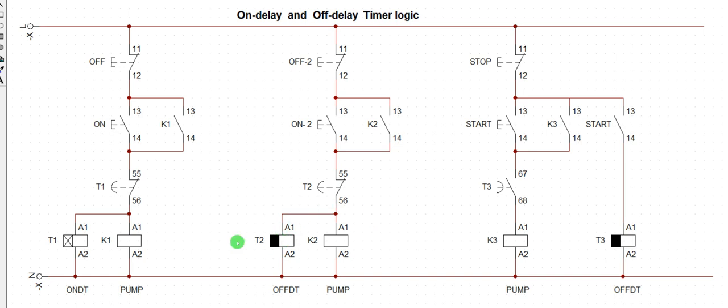So you cannot make a replacement of these two timers in the same logic because their contacts do not function exactly the same. This contact will change state immediately you energize this, but this contact will not change state when you energize this. This contact only changes state when the preset time of the timer elapses.